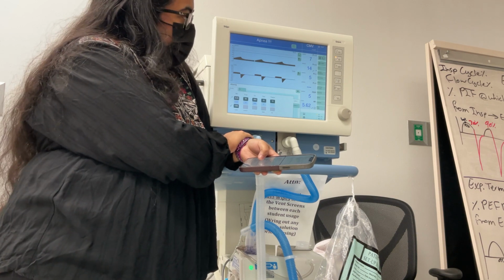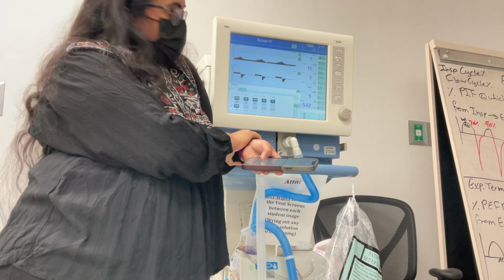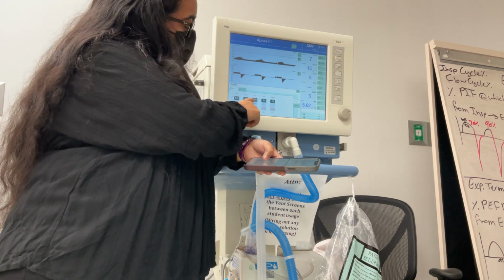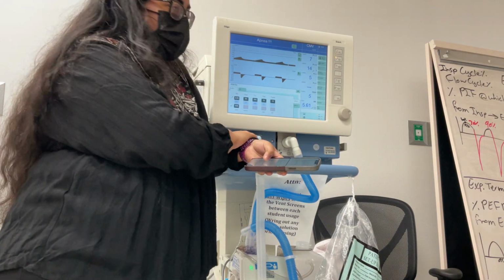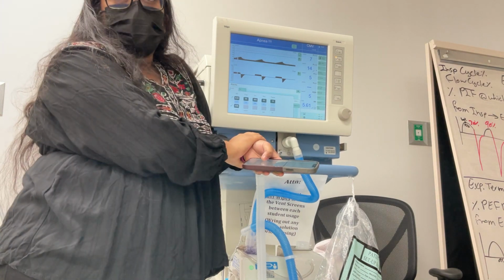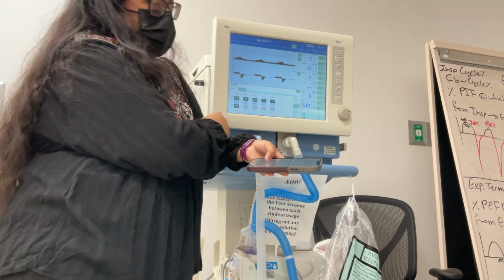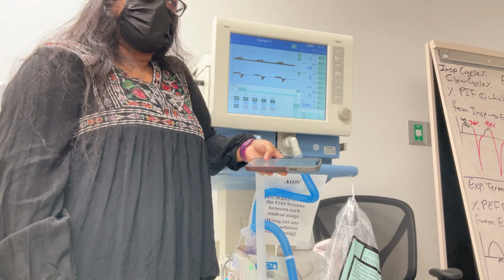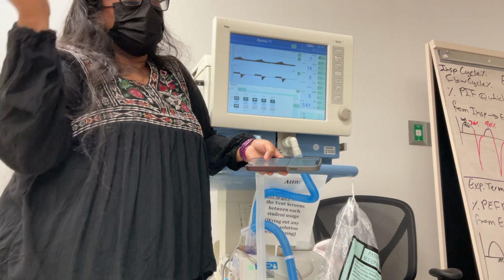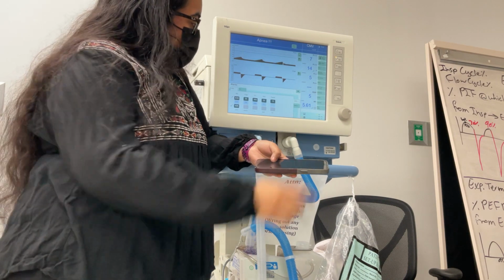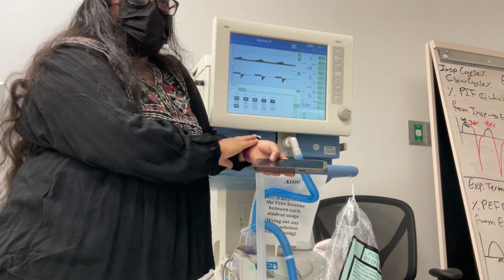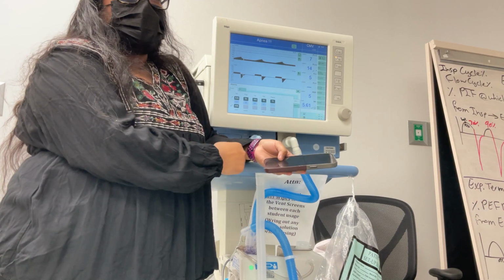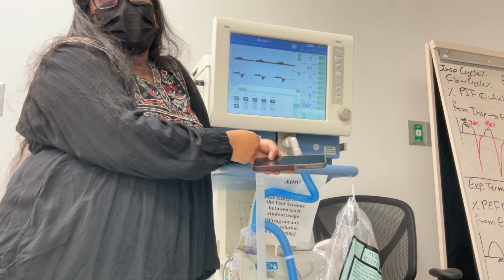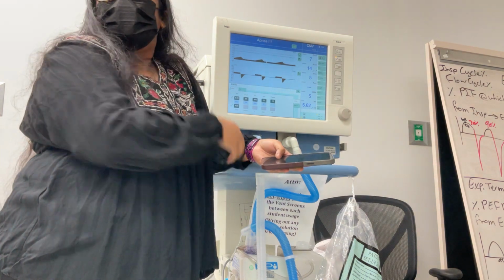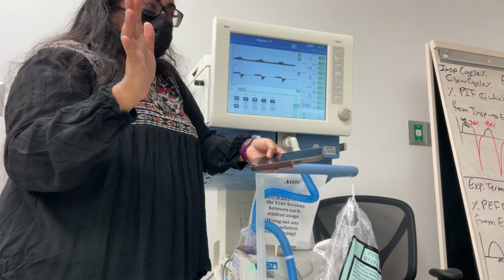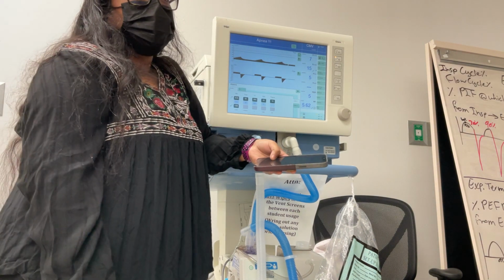High pressure alarm, you'll do 10 to 15 above your monitored pressures. Inspiratory tidal volume, it's like 100 to 200 above the volumes you're getting. We're in volume control right now, so you already know what volume they should be getting, but if you're in pressure control, use your monitored volumes and set it 100 to 200 above. This is going to be your respiratory rate. I usually set it at like 25. You'll see when you get to clinic, it's never going to be 25. It's like 45 or 50 because these people keep hitting those alarms. So it'll be way different in clinic, but for lab, you can do 25 to 30.